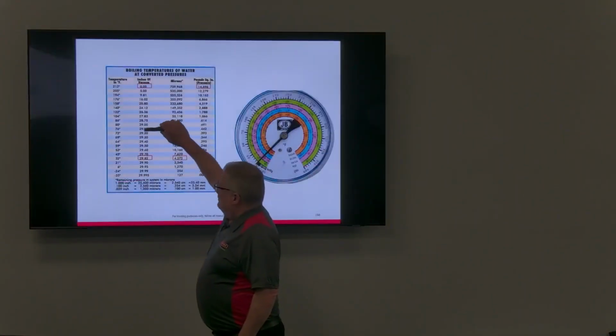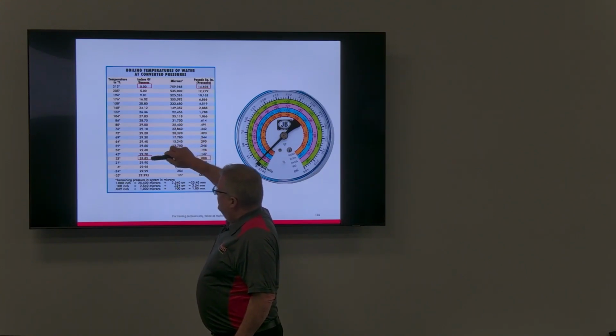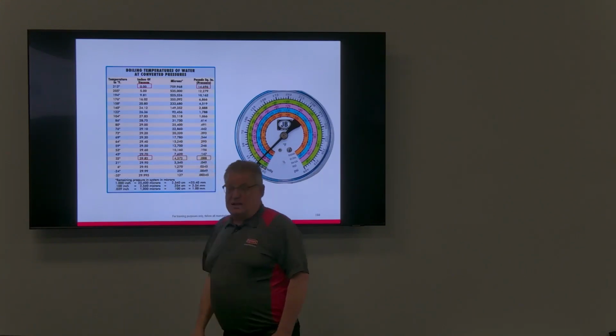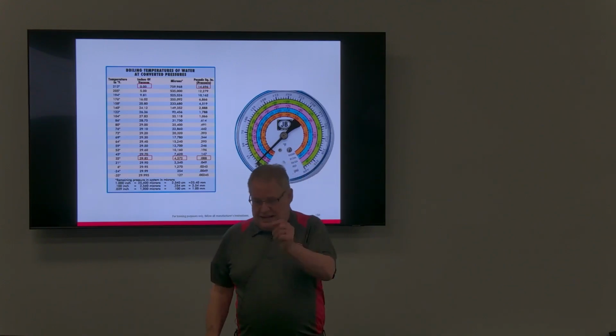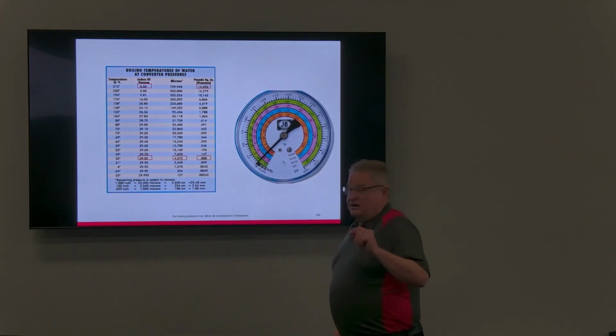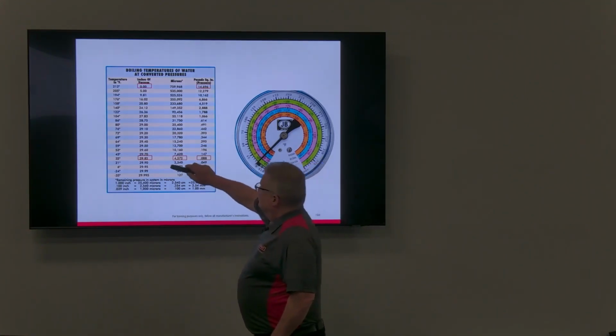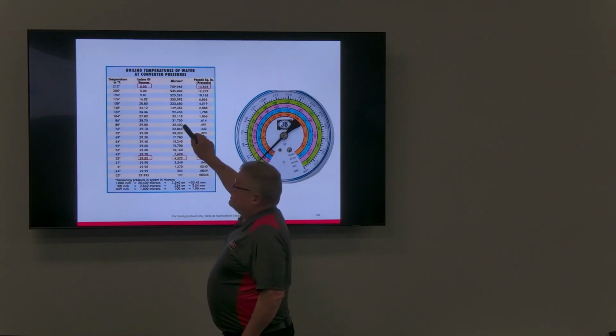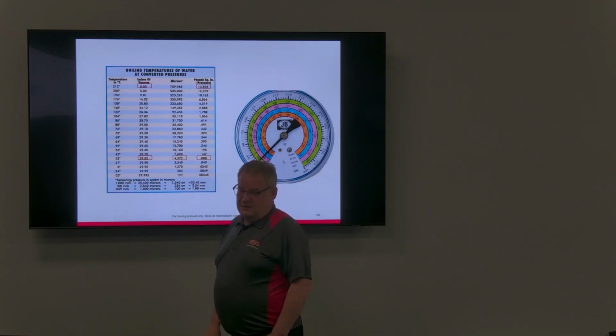And again, everything we're trying to get to on a micron gauge is between about 29.3 and say about 29.7, so all within that last little line. In microns, 29 inches is 25,000 microns, 25,400. So that's why it's so much more accurate.